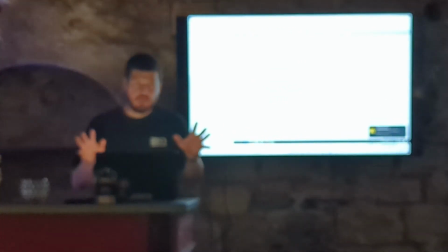Basically, that's a gateway. Here I define a channel, and in my channel I define my devices. Those will be the PLCs. For each of them, I define what I call a tag. A tag is simply a variable, and for each tag, you map it to a device and to a memory address. So for example, this one that I called coil is mapped to the new PLC device at the address 2. Okay, so that's how it works.